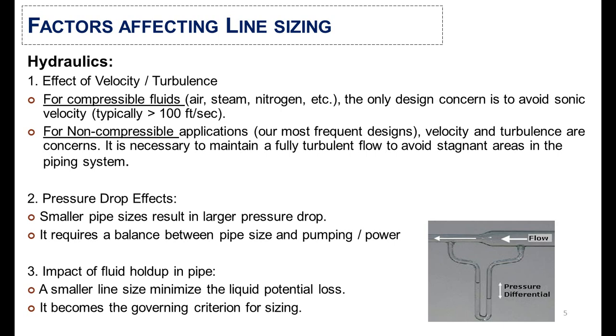To avoid stagnant areas in the piping system, the second hydraulic consideration is pressure drop effects. A smaller pipe size results in a larger pressure drop, so it requires a balance between pipe size and pumping requirements.